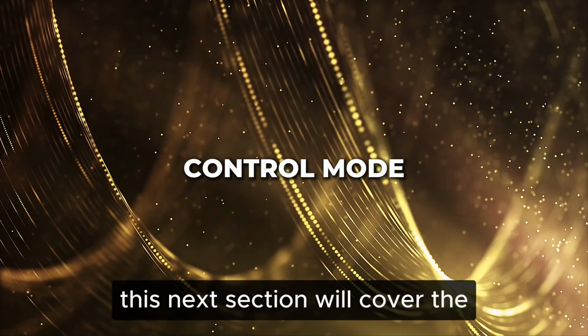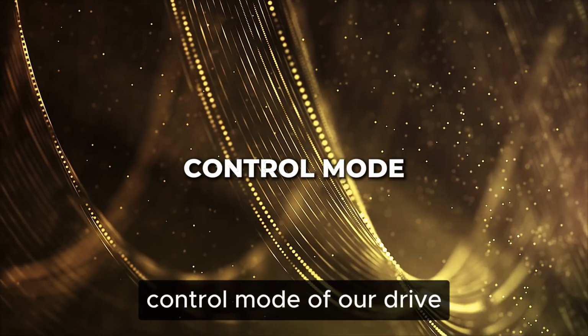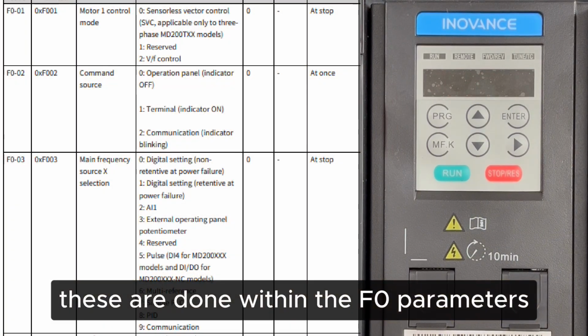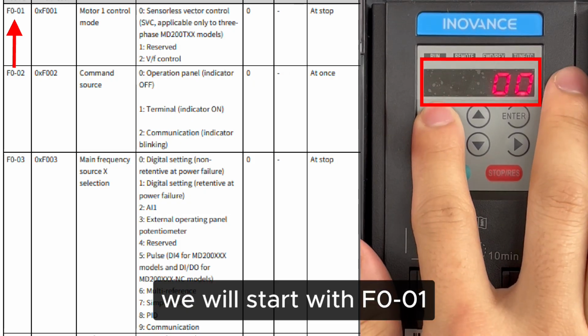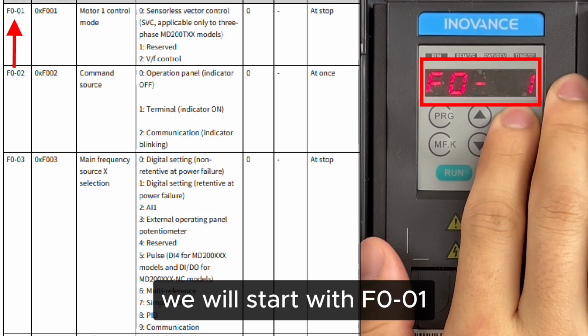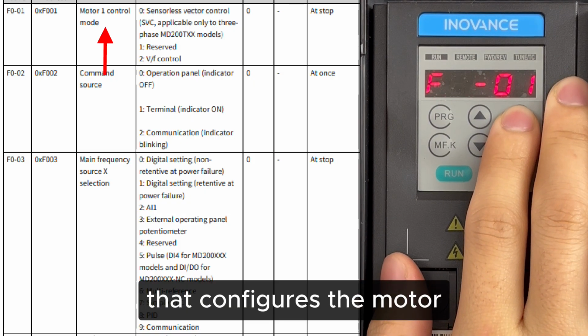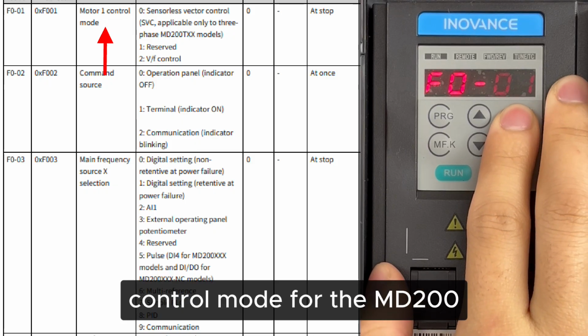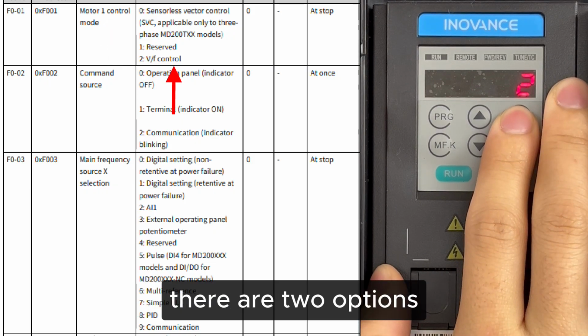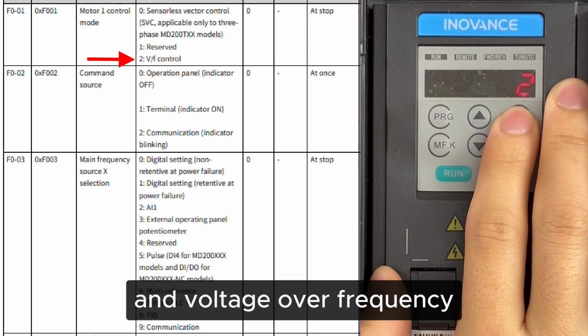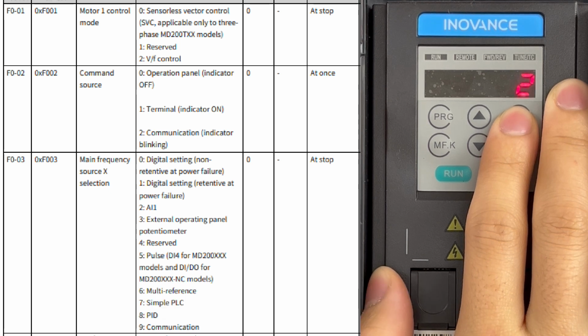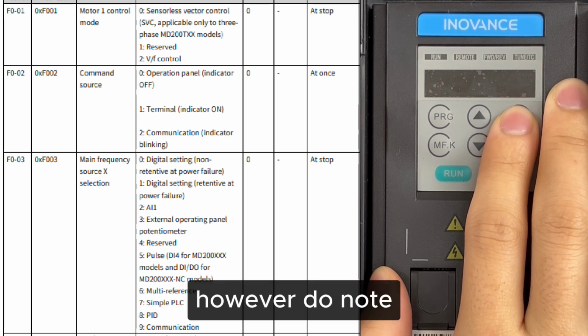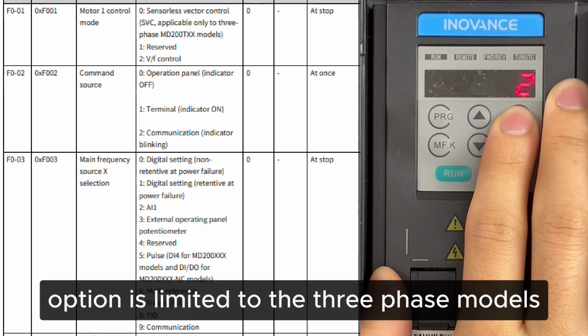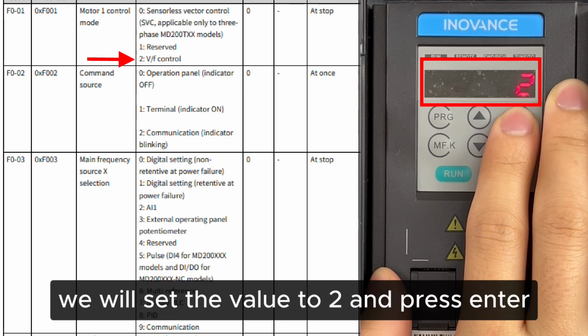This next section will cover the control mode of our drive. These are done within the F0 parameters. We will start with F0-01, which is the parameter that configures the motor control mode. For the MD200, there are two options, sensorless vector and voltage over frequency. However, do note that the sensorless vector option is limited to the 3-phase models. So for our example, we will set the value to 2 and press Enter.